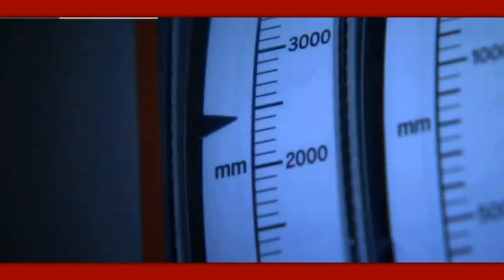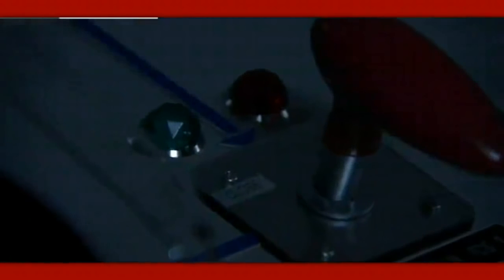The water level was 2.5 meters above top of active fuel. It had dropped nearly 2 meters in just 1 hour. The rapid drop prompted operators in the main control room to suspect the isolation condensers were not working.